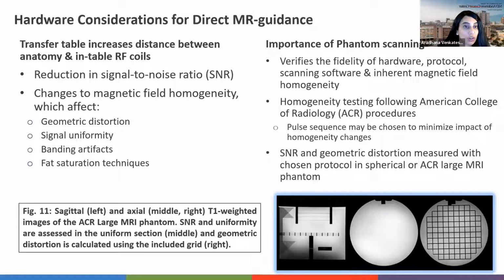We have some images here on this slide that show examples in the lower left of sagittal acquisition, and in the middle and right of the axial acquisition T1 weighted images of our ACR large phantom, which we use for clinical QA of the MR scanner prior to scanning patients. That allows us to assess SNR and the uniformity of the magnetic field. Next slide.